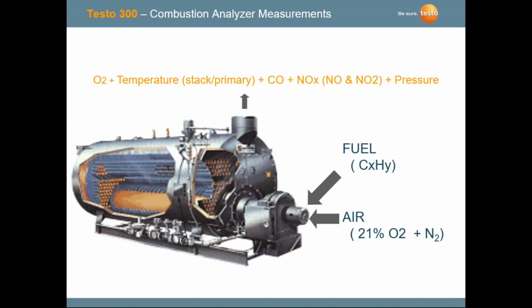We're looking at carbon monoxide. As we all know, carbon monoxide, CO, is a toxic gas. It can be produced primarily with all fuels, and we've got to monitor that carbon monoxide coming out of the flue gases. And then the other measurements that we do are NOx and also pressure, which would be draft. Just want to touch a little bit on NOx there.